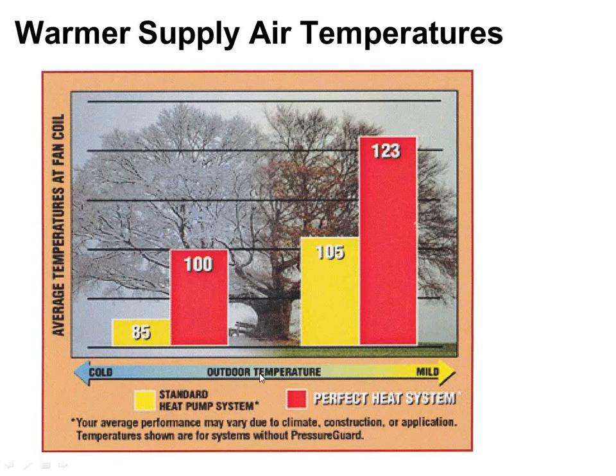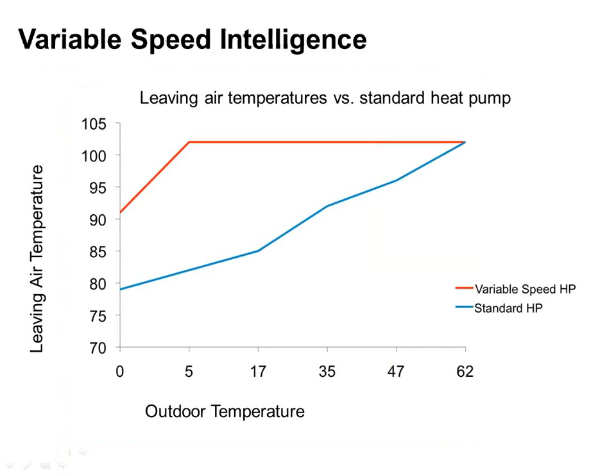But as it gets colder outside and I move left on this chart, it becomes harder and harder to keep the discharge air higher because I have less heat to grab from outdoors. A traditional heat pump kind of falls off and I end up with 80-some degree discharge air, which is not good for the occupants.